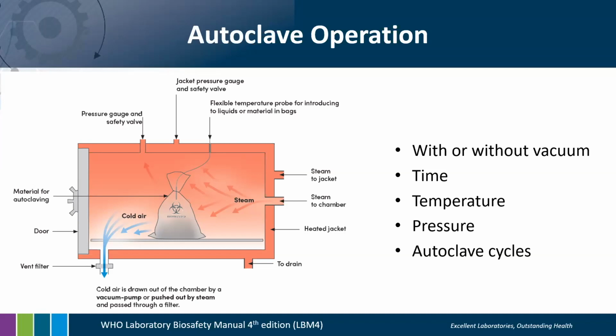An autoclave that has a vacuum pump can more effectively or efficiently remove the air from the autoclave. As the air is being removed, more steam is able to penetrate the autoclave and consequently get in contact with whatever is inside that you want to decontaminate or disinfect. Because of that, say this bag shown here in this picture needs to be open, and you see an arrow showing the steam coming in. So that's really important for the hot steam to get in contact with whatever you intend to be decontaminated.